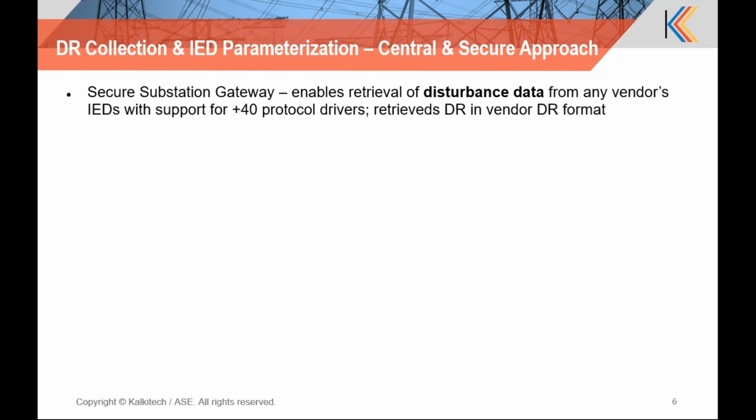If there is an Alstom or Areva system, there can be the Courier format, which represents the disturbance record as well as the protocol transmission. Also, there are custom mechanisms like GE Modbus. GE relays use their own customized Modbus protocol for DR collection, and its representation of data is in a specific format.